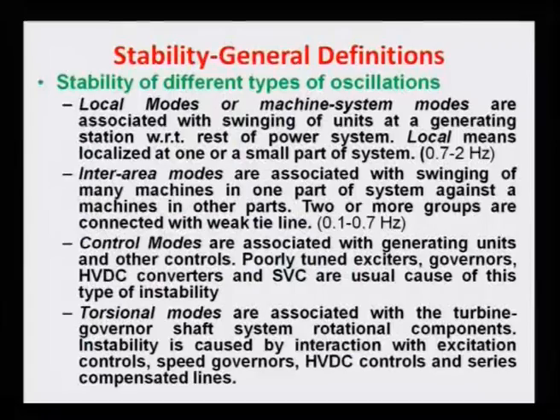The third category of oscillation is the control modes of oscillation, and these are associated with the generating units and other controls, such as poorly tuned exciters, governors, HVDC converters, static var compensators or STATCOMs, which are usually the cause of this type of instability. So the control actions of the various controllers, including HVDC converter control, FACTS devices control, or even the generator control itself, including the exciters as well as the governor controls, may lead to the control modes of oscillation.